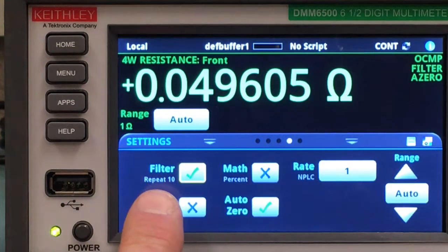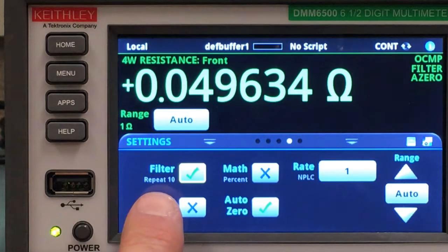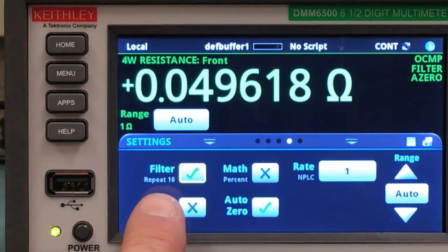You might be able to see in the text down here that we have a 10-sample filter applied. It's a repeating filter, so it will capture 10 readings and then give you an update.